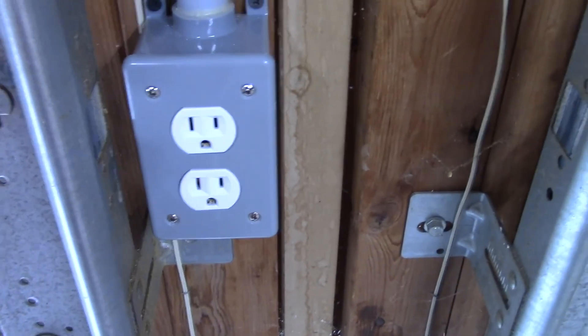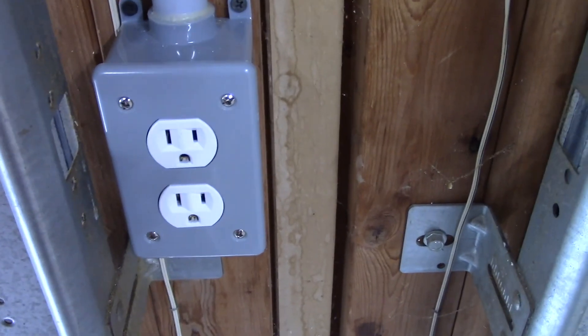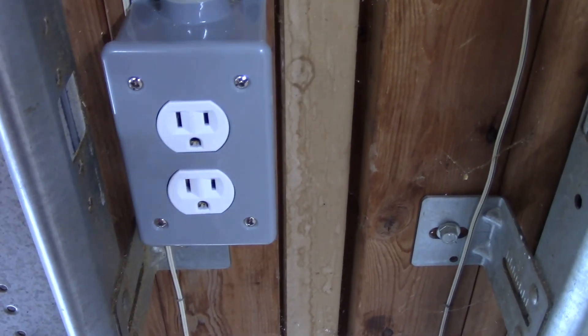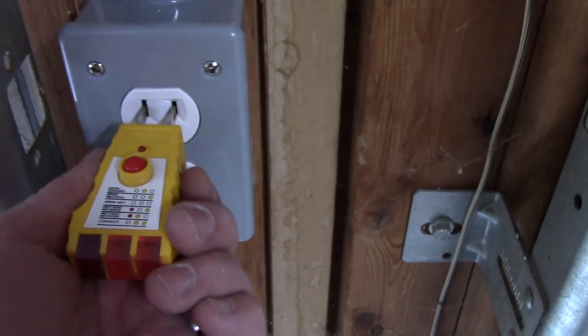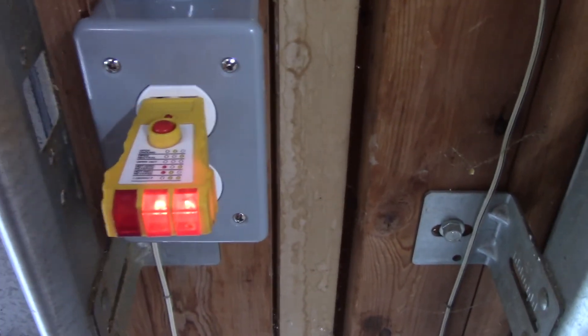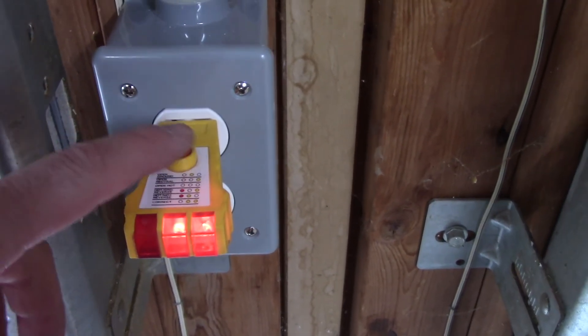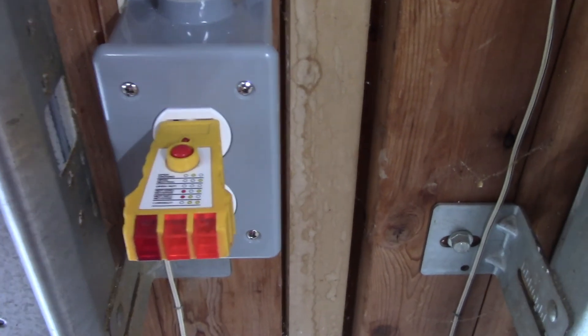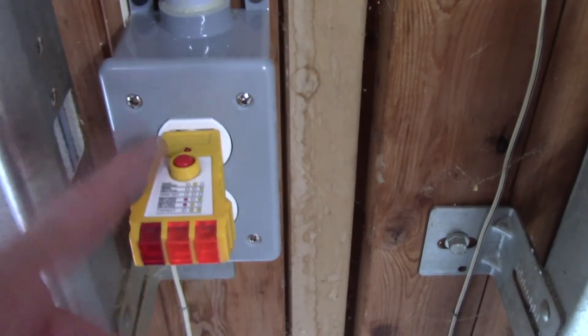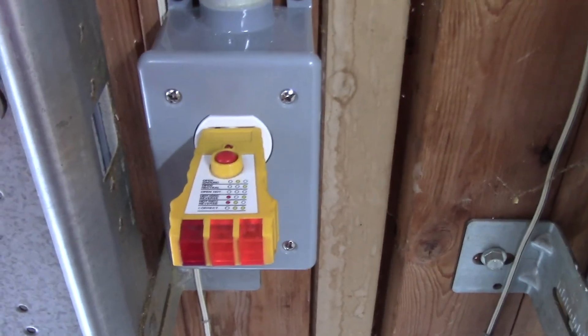This outlet here is wired downstream or on the load side of that GFCI outlet I put in. So if I put the tester in here, I have the two orange lights. And if I hit the button, it trips the GFCI. So this outlet in the garage is also protected from that GFCI.